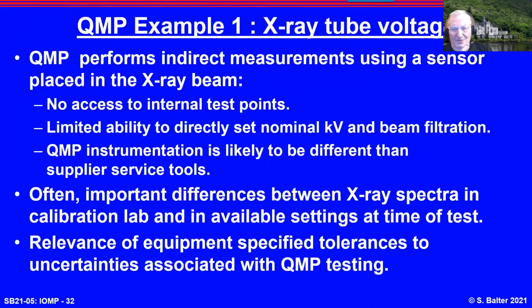So here's the tube voltage. I'm measuring the voltage, putting a sensor in the X-ray beam. I can't get at the internal test points because it's locked, it's dangerous. I have no way of setting the kV and beam filtration. This is improving in newer systems that will have a QA mode. And hopefully this becomes more fully deployed in the next couple of years.